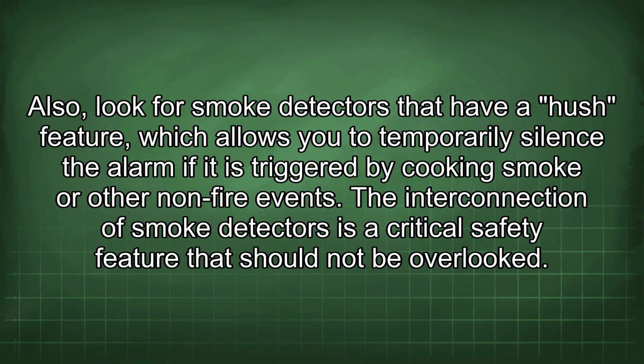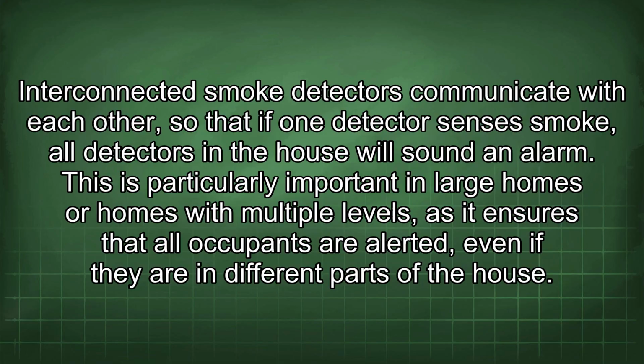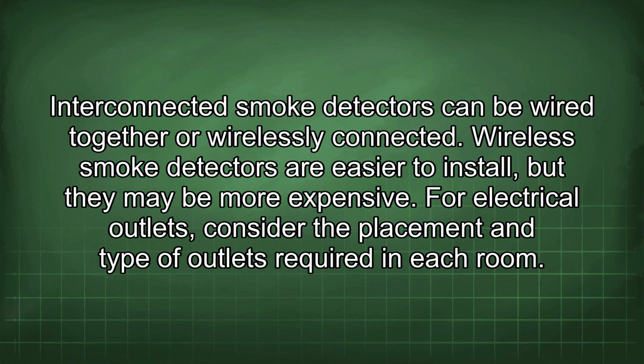The interconnection of smoke detectors is a critical safety feature that should not be overlooked. Interconnected smoke detectors communicate with each other, so that if one detector senses smoke, all detectors in the house will sound an alarm. This is particularly important in large homes or homes with multiple levels, as it ensures that all occupants are alerted, even if they are in different parts of the house. Interconnected smoke detectors can be wired together or wirelessly connected. Wireless smoke detectors are easier to install, but they may be more expensive.